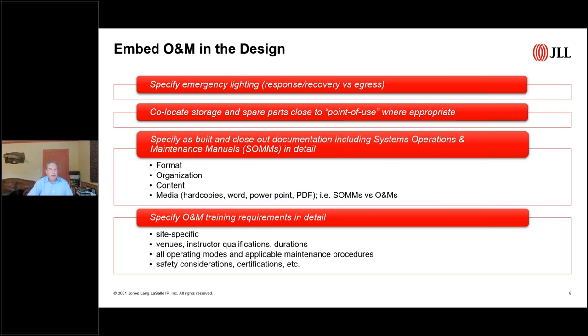Another thing is to co-locate storage and spare parts close to the point of use where appropriate. If it's small stuff, keeping it in a room anywhere isn't a big deal. But if you're talking about a 300-pound motor that has to be rigged and transported into place, it'd be nice if it's located close to the point of use, like a pump or chiller, rather than transporting it through an occupied building with the risk of damaging something.